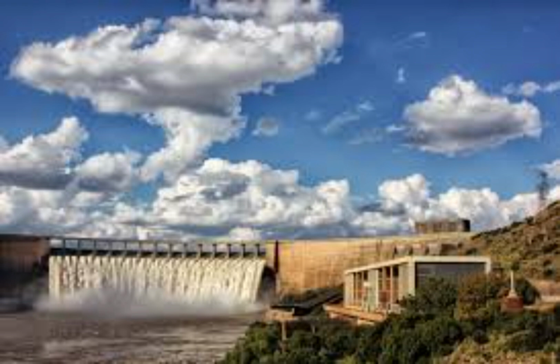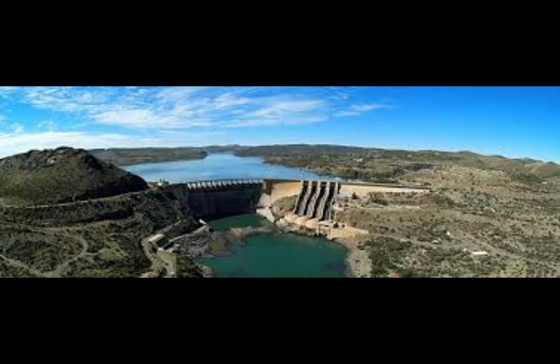5. Hydroelectricity. 1. The Gariep Power Station is a 360 megawatts hydroelectric power plant located on the Orange River in the Northern Cape province of South Africa, operating as part of the Orange River Water Scheme and owned by Eskom. 2. Vanderkloof Power Station. The underground machine hall houses two 120 megawatts turbine generators, each consisting of a medium-head vertical Francis water turbine, directly coupled to an umbrella-type generator. The water to drive the turbine is conveyed from the dam through 7 m diameter steel-lined penstocks to the turbine's spiral casing.